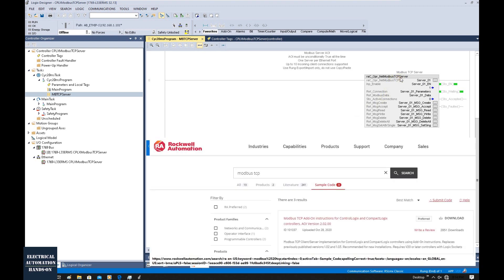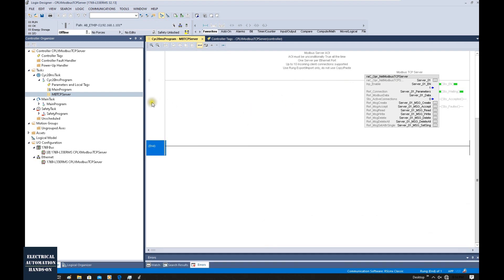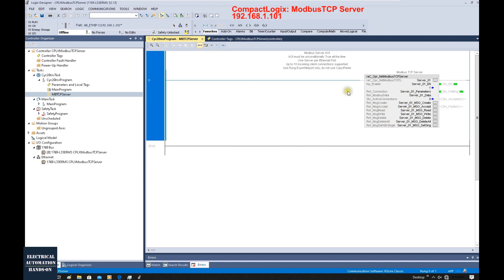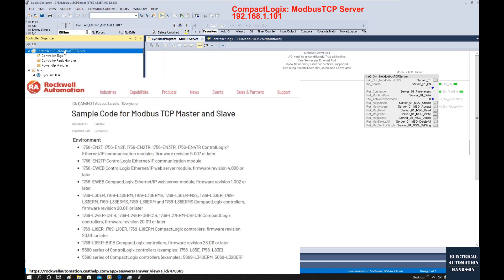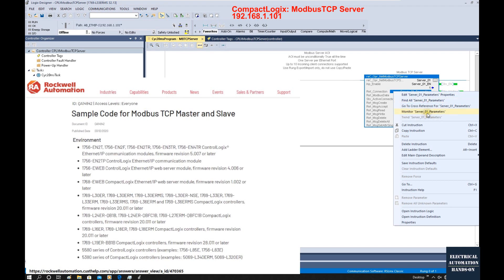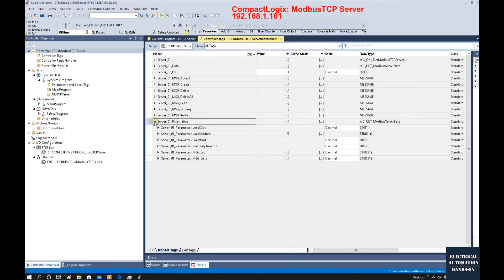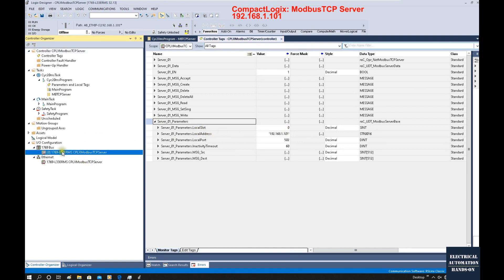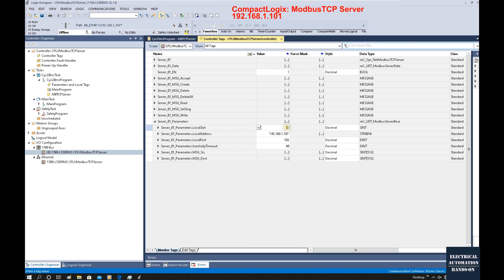To implement the Modbus TCP server function on the Allen-Bradley side, we need to download the AOI and then import it. Once we import this AOI, it will show the Modbus TCP server function block. This controller is a CompactLogix and its IP is 192.168.1.101. Let's check the Modbus TCP server settings. Go to the connection, right-click the parameter, click monitor and expand. The local slot is 0, meaning we are using the built-in Ethernet port from this Allen-Bradley controller — a 1769-L33 CompactLogix controller. This port index is 0, so we type 0 in the local slot Ethernet port field.